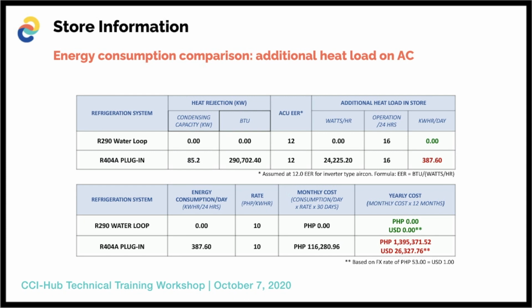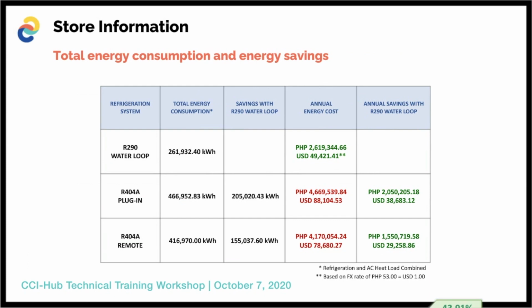And then finally, these R290 Waterloop systems are not only very efficient, they also have inverter systems in them for both the dry cooler, the pumps, as well as the plug-in AHT R290 systems. Because of the efficient nature of these systems, this is a slide that was also presented in Atmosphere. These are calculated numbers, unfortunately. We're still collecting the actual numbers, but we calculated a savings of approximately 43% energy savings compared to their plug-in systems, and approximately 37% energy savings compared to comparable remote systems.